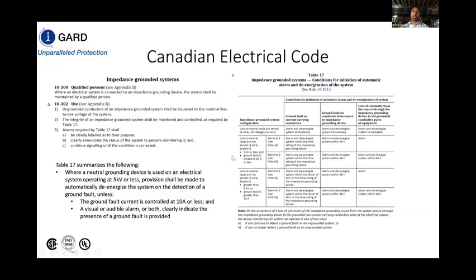A lot of consultants are taking advantage of the fact that in a 3-phase 3-wire system where we're 5 kV or less, or if ground fault current is limited to 10 amps or less, we have the ability to alarm the ground fault without tripping, provided that we're using a continuous rated resistor. Because here it stipulates you alarm and de-energize the system within the time rating of the impedance grounding device. But if the time rating of the impedance grounding device is continuous, then we only have to alarm the condition of fault and continue with the process without tripping anything.